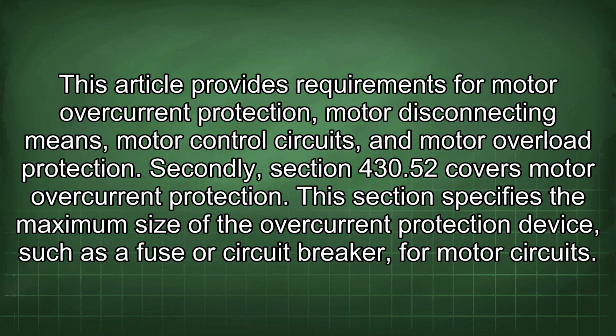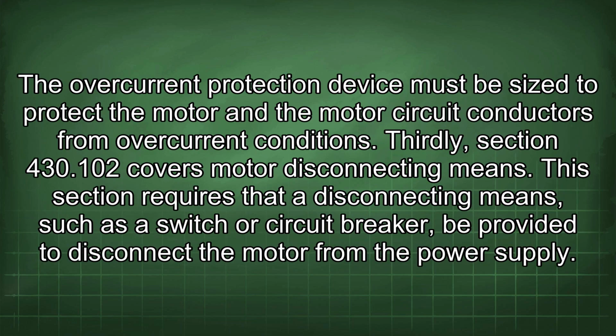This article provides requirements for motor overcurrent protection, motor disconnecting means, motor control circuits, and motor overload protection. Secondly, Section 430.52 covers motor overcurrent protection. This section specifies the maximum size of the overcurrent protection device, such as a fuse or circuit breaker, for motor circuits. The overcurrent protection device must be sized to protect the motor and the motor circuit conductors from overcurrent conditions.